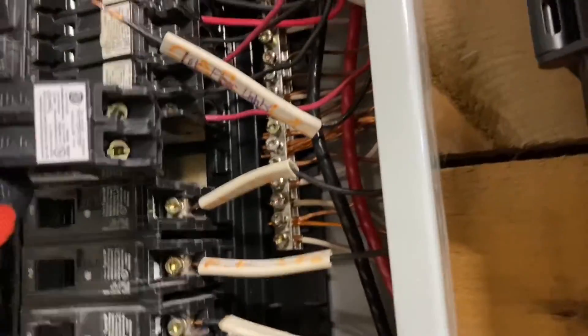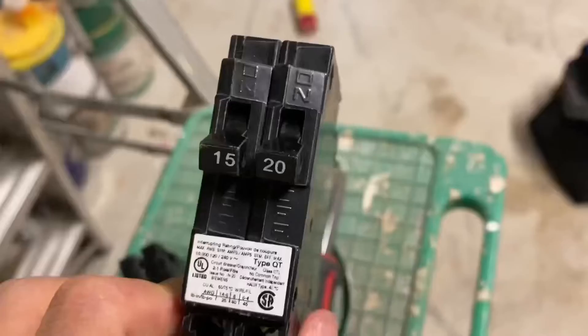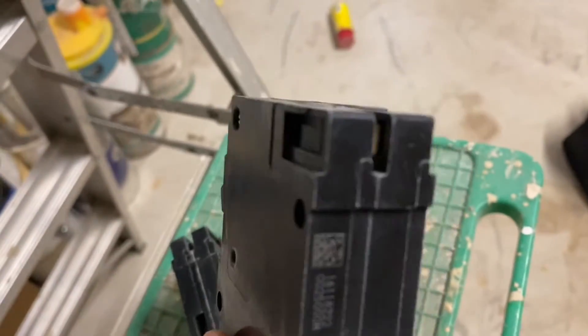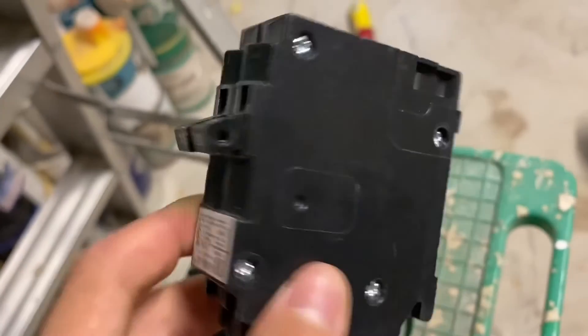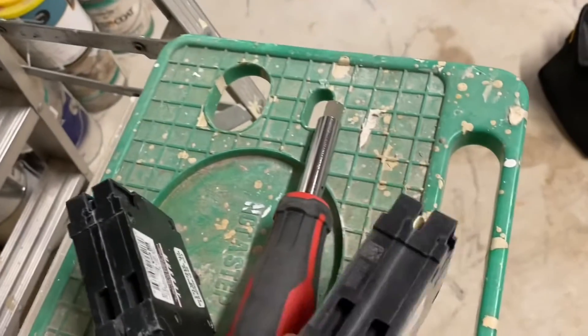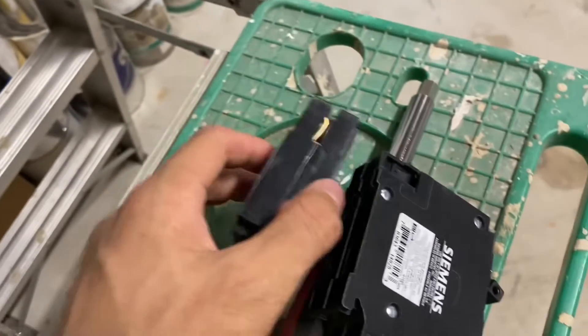At this point we can go ahead and put in our new breaker — it just hooks up there. Make sure it's off before you plug it in and then just press. I got concerned because the breaker would not fit. The reason it wouldn't fit is because I bought the wrong type of breaker — I bought a CTL style breaker, but this panel does not accept the newer breakers, tandem or not. I needed the more expensive non-CTL style breaker.